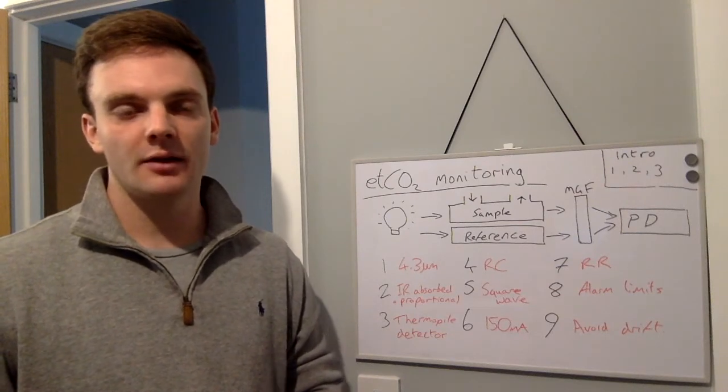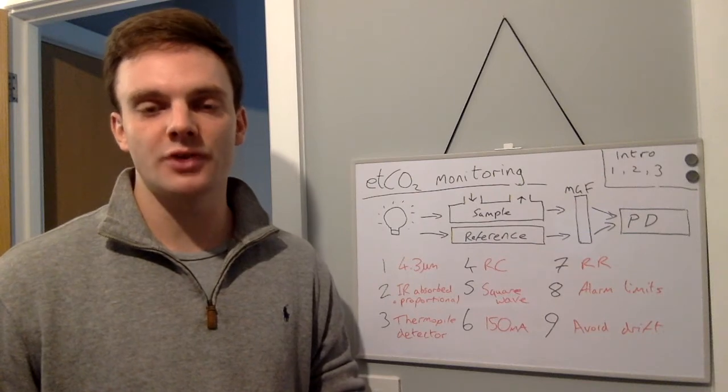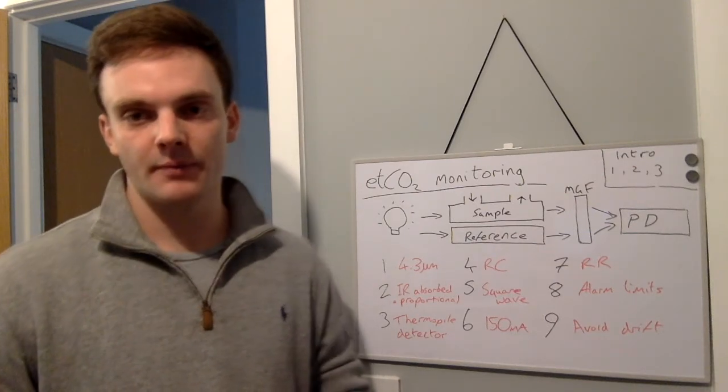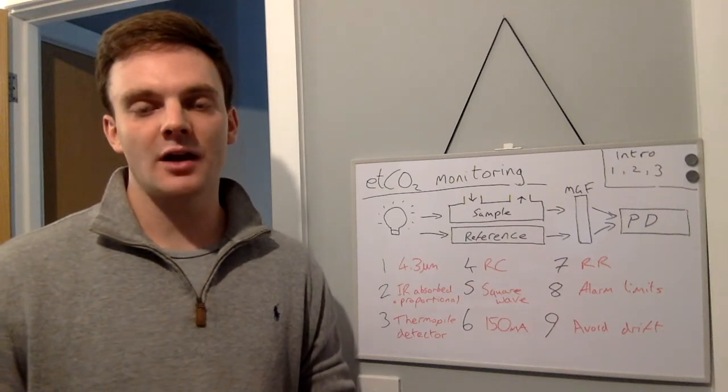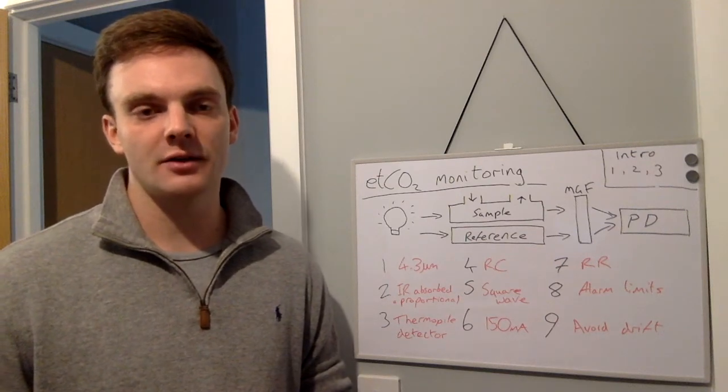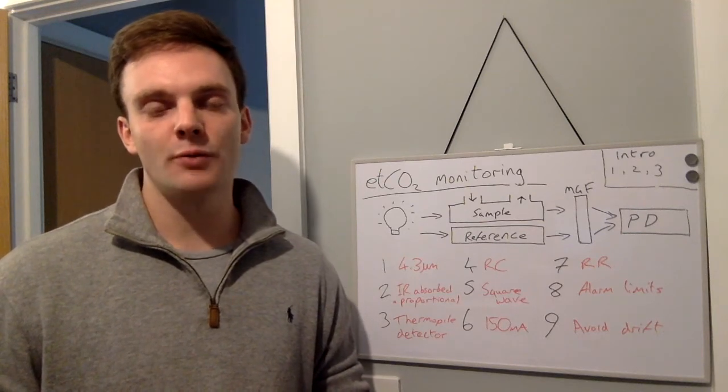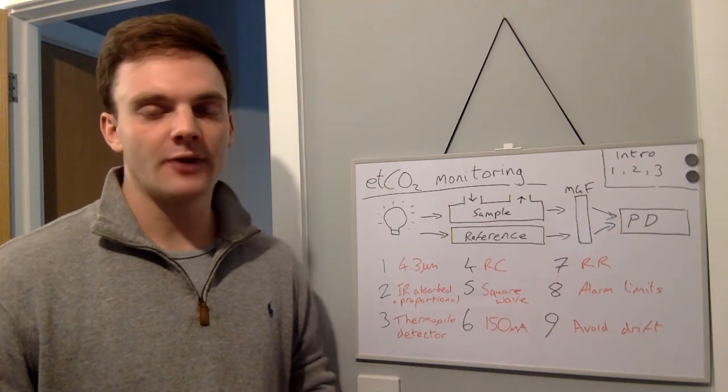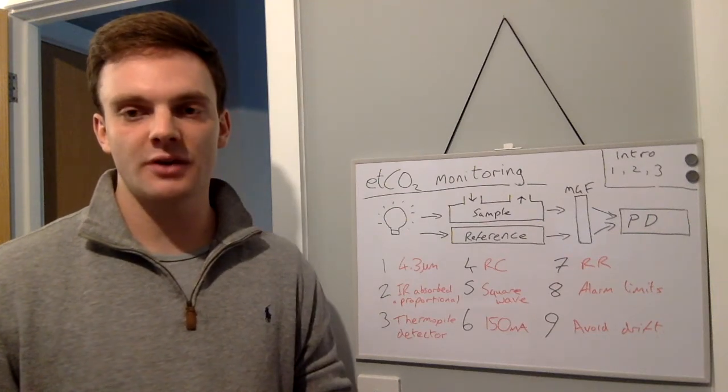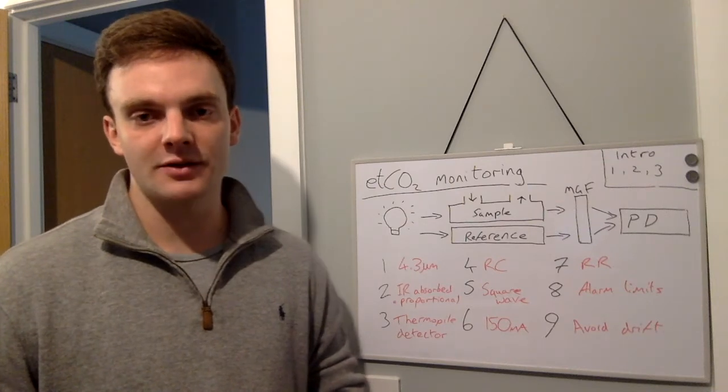The first point being that end tidal carbon dioxide analysers are used to monitor end tidal CO2. The second point is that these analysers utilize the fact that molecules with two dissimilar atoms absorb infrared light at a specific wavelength. And the third point is that end tidal CO2 analysers can either be mainstream or sidestream analysers.